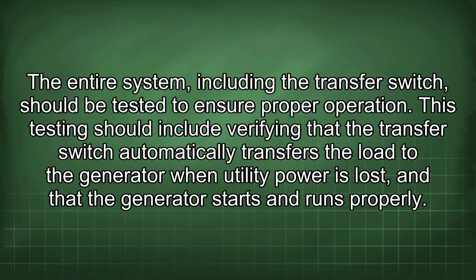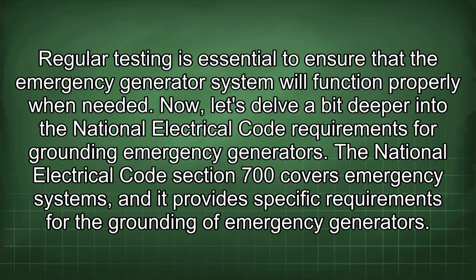The entire system, including the transfer switch, should be tested to ensure proper operation. This testing should include verifying that the transfer switch automatically transfers the load to the generator when utility power is lost and that the generator starts and runs properly. Regular testing is essential to ensure that the emergency generator system will function properly when needed.